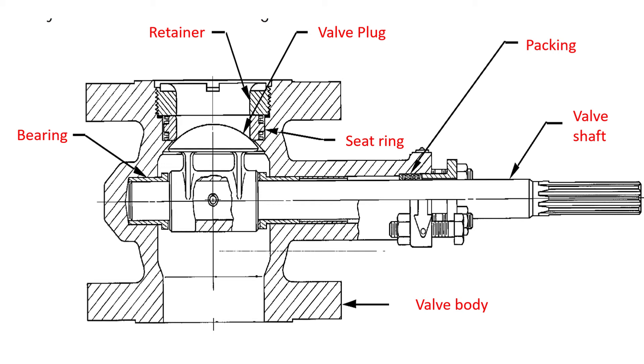The valve shaft is the one that transmits torque to the valve plug. Because the process fluid may have high piping pressure, the valve shaft must deliver the required torque to the valve plug to act against that pressure and throttle the process fluid.